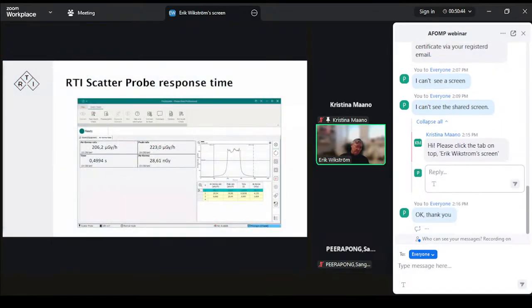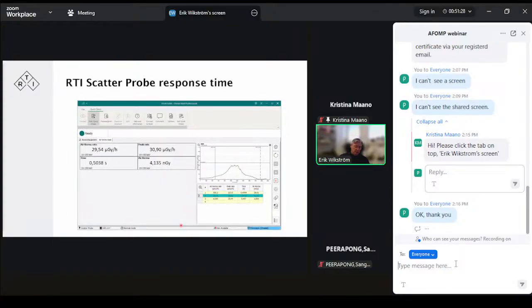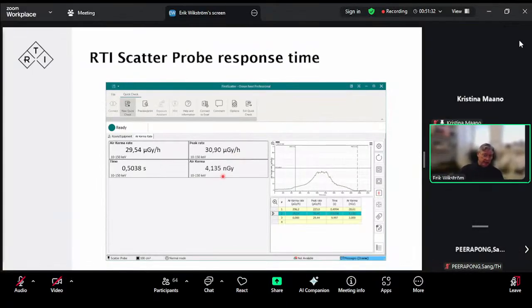And looking at the response time as well, we see here the display that we have for the RTI scatter probe. This is a reading that we're doing from a leakage. It turns out that it's 28 nanogray, so you see it's quite low. But look at the response time that we have here. From the start, the triggering, and this is a self-trigger, the automatic built-in trigger, it's less than half a second until we're up to the maximum of the output. The maximum, not only 95%, but the maximum. If we look at a lower dose rate, a weaker signal, here we're playing with something that is 30 microgray, and the total dosage of 4 nanogray, which is very, very little.